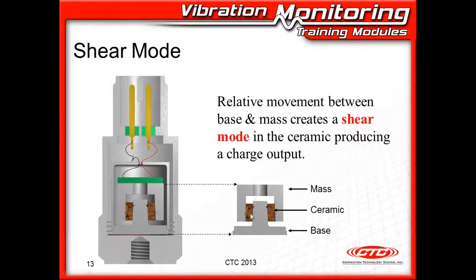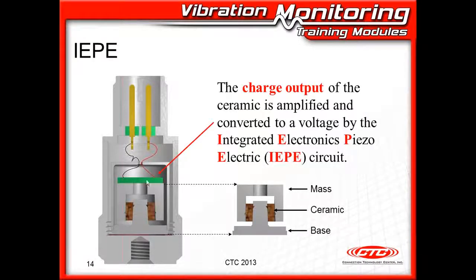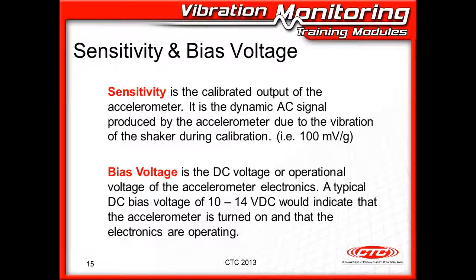Just as we look a little bit at our pedestal here, our post, and our ceramic and our mass, it's these three parts that really form the core of the accelerometer. The vibration is transmitted up through the post. The mass is trying not to move, and because of that difference in vibration and mass, you have a shearing mode taking place in the ceramic. So these are shear mode accelerometers, and the shearing of this ceramic provides an electrical charge. And that charge is converted to a voltage with this amplifier board right here. So the charge output of the ceramic is amplified and converted to a voltage by our integrated electronic piezoelectric circuit, our IEPE circuit. This is a standard 2-wire technology that exists all around the world and is used by all the major manufacturers of not only sensors but data collectors.